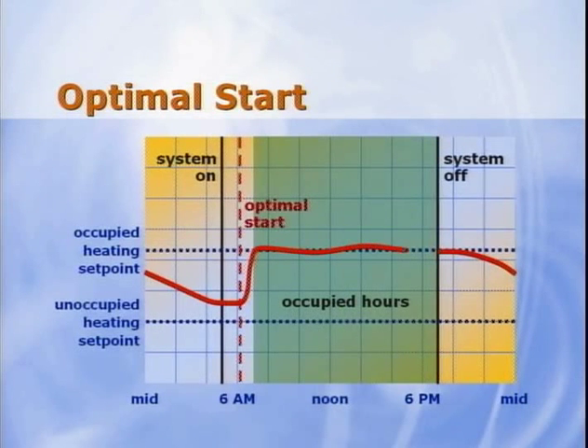However, there is a more energy efficient method. An alternative is a strategy called optimal start. As Justin mentioned earlier, ASHRAE 90.1 requires an optimal start strategy when the system design airflow is greater than 10,000 CFM. For optimal start logic, a building automation system is used to determine the length of time required to bring the zones from their current unoccupied state temperatures to the occupied set point temperature. So, the system waits as long as possible before starting. This minimizes system runtime and prevents the zones reaching the occupied set point temperature prematurely. The appropriate comfort set point is reached just in time for occupancy.